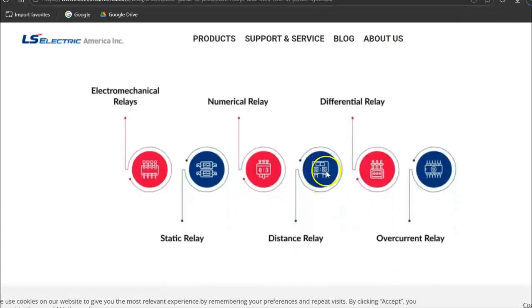Now, many different types. The older ones, and one of the ones you'll be working with in Lab 11, is an electromechanical one. They don't take any power, they just work, and they will trip, and you can set the tripping for instantaneous or for a timed trip, which is like an overload. You can have numerical relays. Distance relays, they'll monitor the impedance of a line, and if it drops too low, they know that there's a fault to ground. Differential, you can check the current or the voltage on the upstream side of a relay and the downstream side. And if there's a difference, meaning that something on the secondary side shorted out and the voltage is lower, it'll trip. And of course, the overcurrent trip as well.